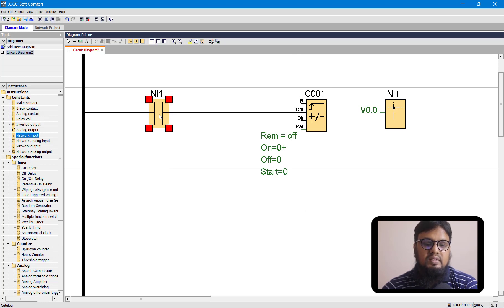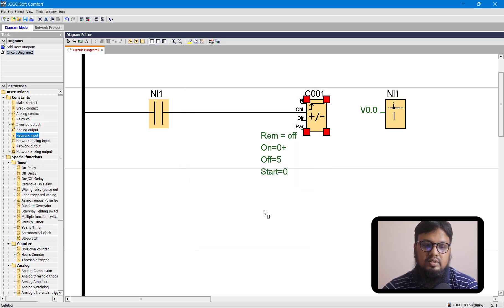We have connected the diffuse sensor as input to the up-down counter. We also need to configure this up-down counter so it can turn on at a certain value and turn off at a certain value. We will start the conveyor at zero count, and whenever we reach a count of five objects, it will stop the conveyor belt. So we will put zero at the on value and five at the off value. Let's hit OK.